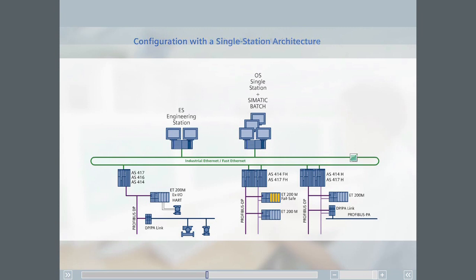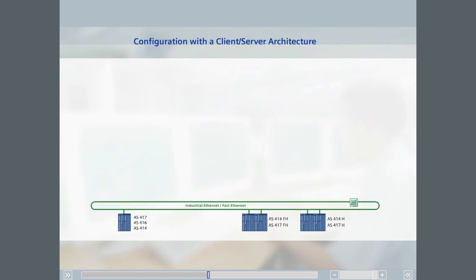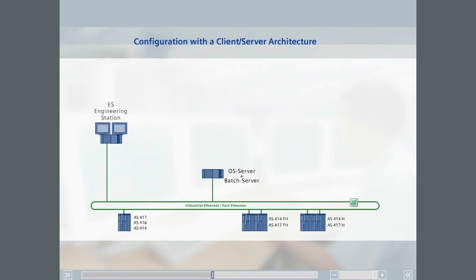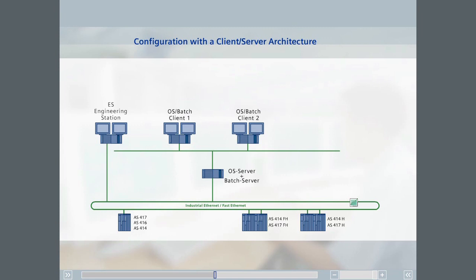In the second example, two operators will control and monitor the system at the same time. The automation systems always have one engineering station connected at all times. A client-server architecture is installed for operator control and monitoring and for SIMATIC Batch. The OS server is connected to the automation stations over the system bus. There is also a terminal bus, over which the two clients are connected and at which the two operators work.